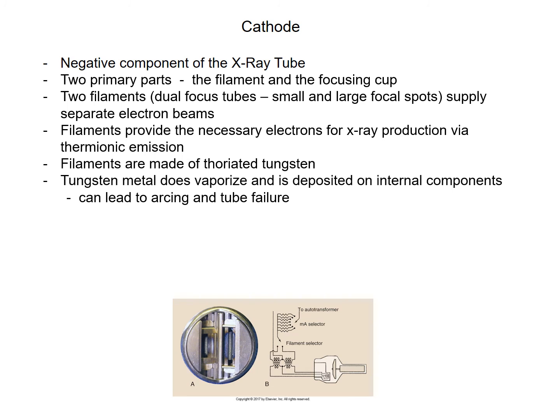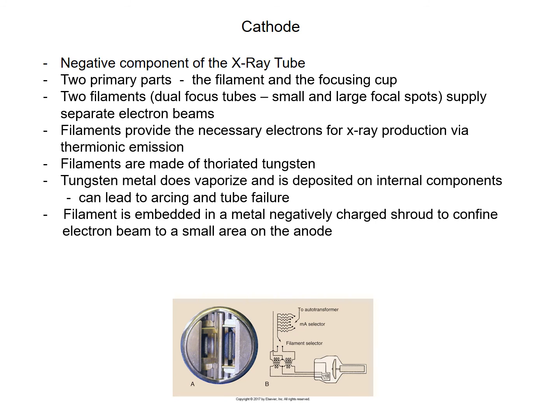Tungsten metal does vaporize, and it is deposited on the internal components of the glass envelope. Itself, it can lead to arcing, which eventually can lead to tube failure. Remember, we just saw that if you have metal tubes, you're less likely to have tube failure because of arcing not occurring. The filament is embedded in a metal negatively charged shroud to confine the electron beam to a small area on the anode. Remember, as these electrons are being boiled off, they need to be kept around the filament until we apply the kilovoltage to cause them to move toward the anode.